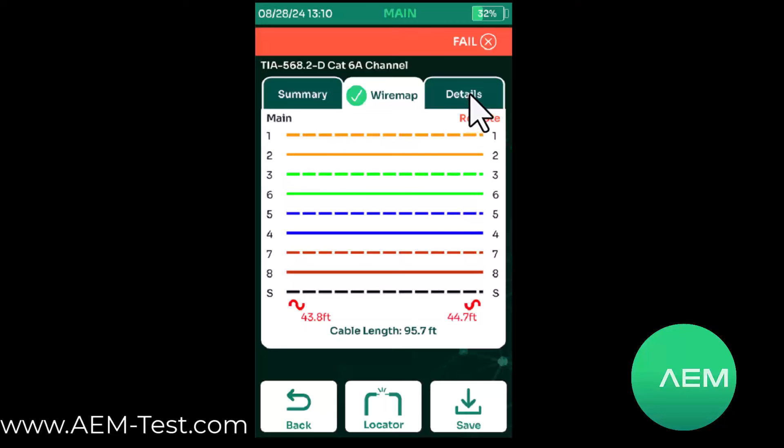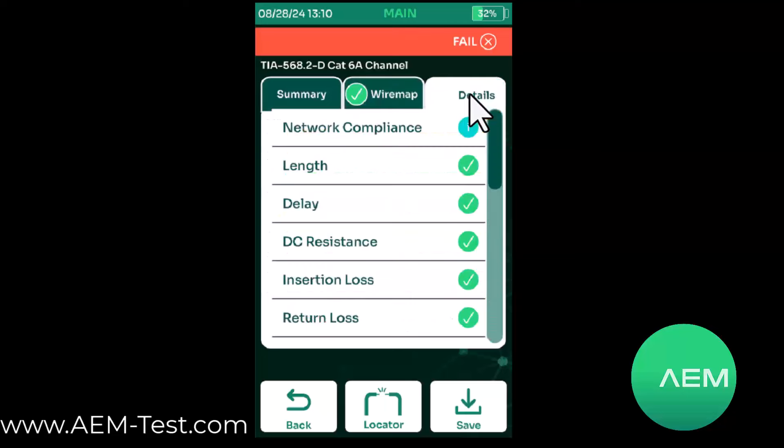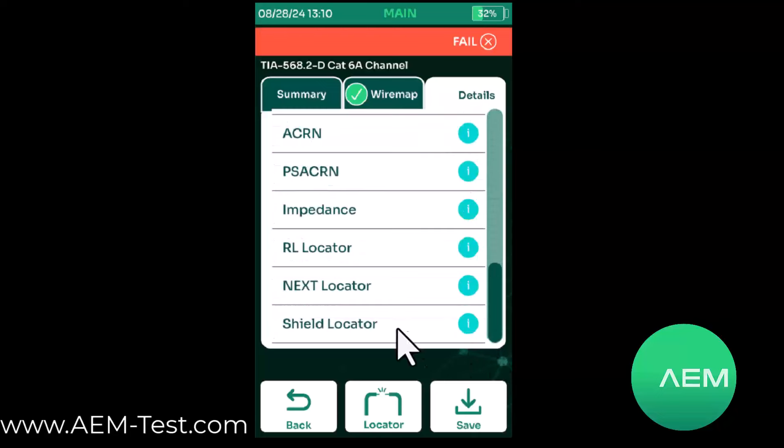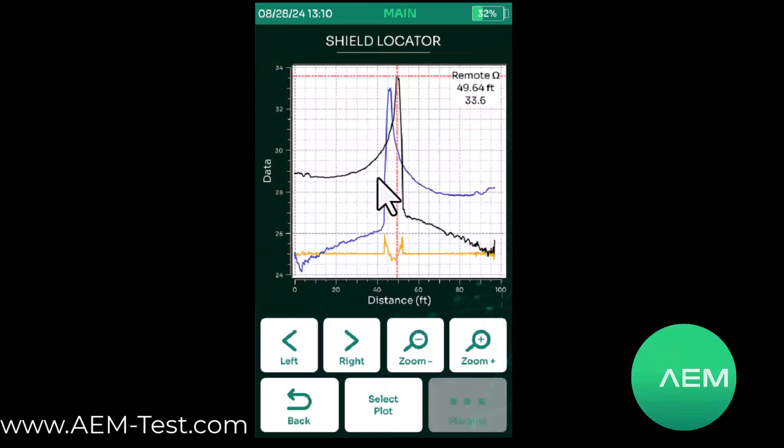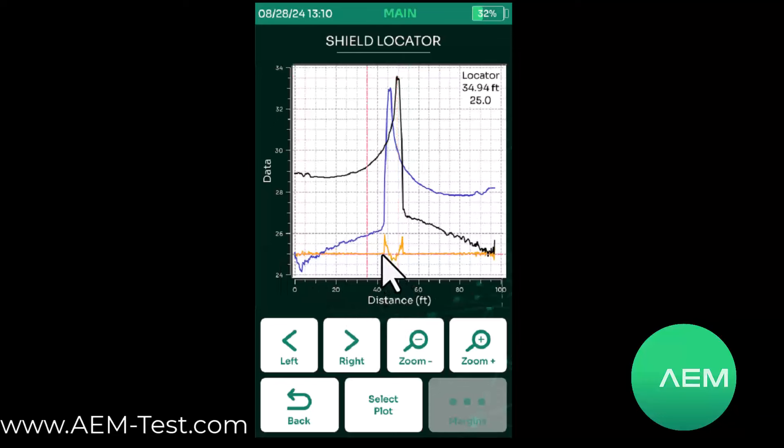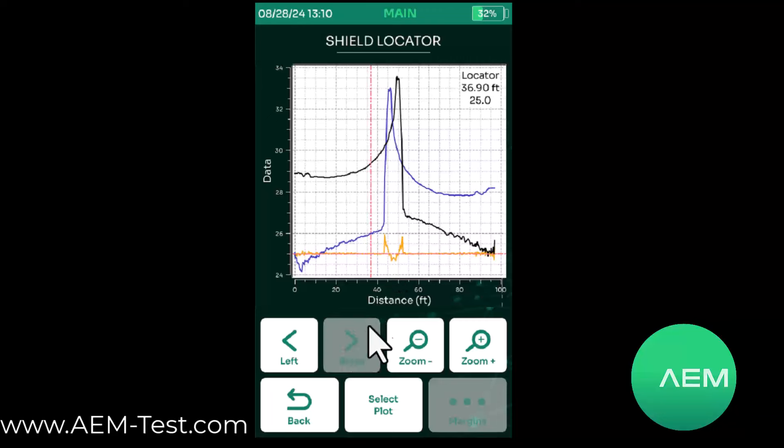I'm going to go to my details tab and scroll down to shield locator. When we pull up shield locator, here we see a TDR trace of the shield and the distance to the event. If I click where this first event begins, right in here, we'll get zeroed in on that. I see that, yes, about 43 feet away is where this starts.